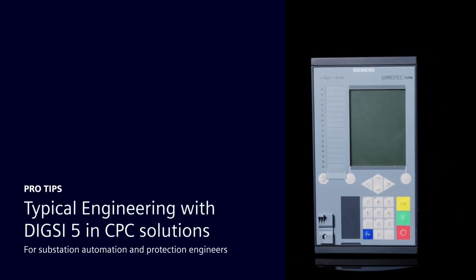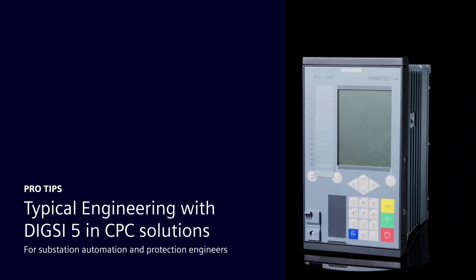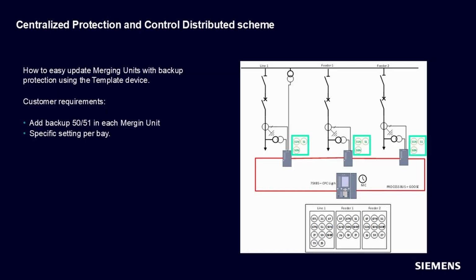Today, I'd like to present to you an interesting application in DIGSI using typical engineering. In this example, we will add overcurrent protection functions to each of the merging units in an existing substation as backup protection. Let's see how easy it is using templates in DIGSI.